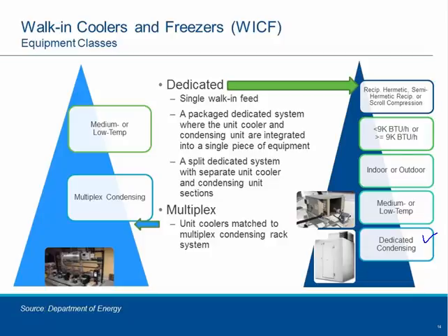It starts with, is it dedicated condensing? Is it a medium temp or a low temp? Is the condensing unit located indoor or outdoor? And the classification of, is it less than or greater than 9,000 BTU an hour in cooling capacity? This regulation actually takes it a step further and looks at it in terms of the compression technology required. Reciprocating hermetic is a compressor, a semi-hermetic reciprocating is another type of compressor, as well as scroll compression technology that will be used for this. And each one of these, depending upon what type of system is in the architecture, will actually have an AWEF value placed on it.